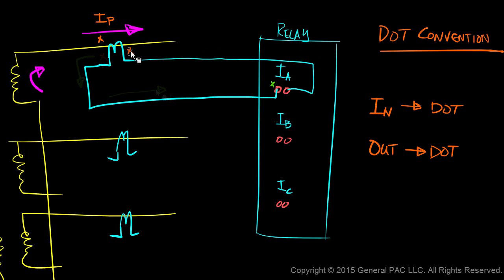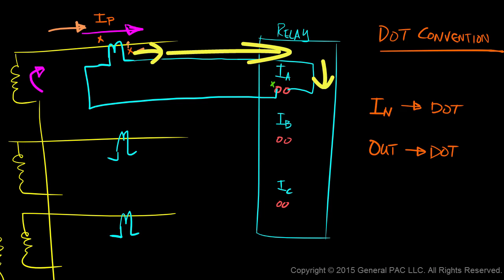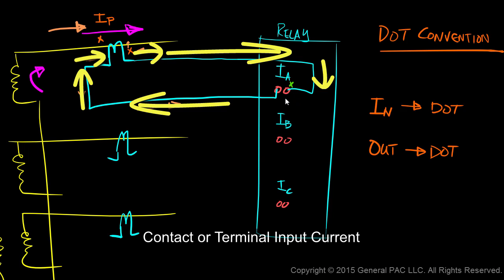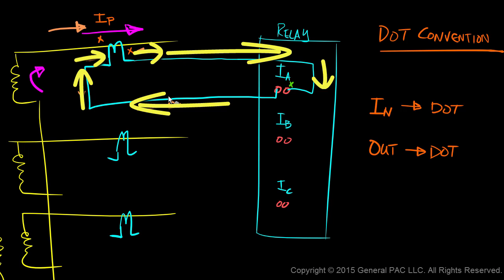Suppose now we have the dot on this side of the transformer — how would we interpret that? Current that flows into the dot on the primary side must flow out of the dot on the secondary side. The dot comes out like that, so current flows out of the dot on the secondary side and makes that loop in this direction. Because we have the dot on this side now, we should expect the polarity side to be like this — this is the polarity contact of our relay.